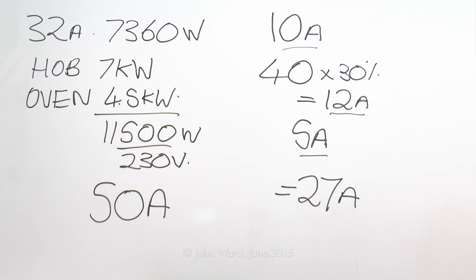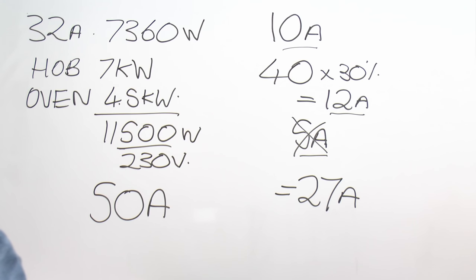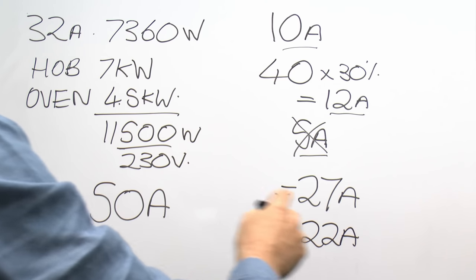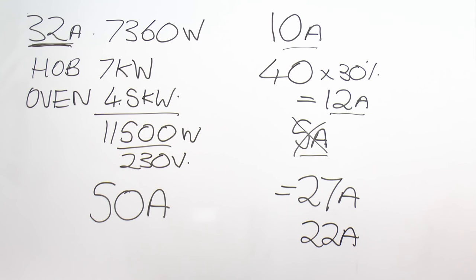If the calculated figure approached the 32A limit, simply removing the socket outlet from the cooker control unit saves another 5A — bringing it to 22A, a full 10A below the circuit breaker rating. It doesn't matter whether it's a freestanding cooker, a separate hob and double oven, or a hob with two single ovens — the same principle applies: add up the total ratings and apply the formula.